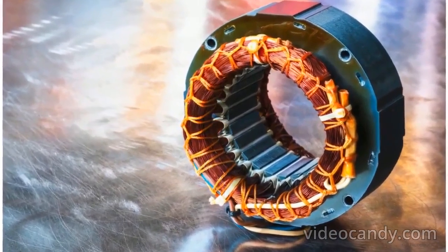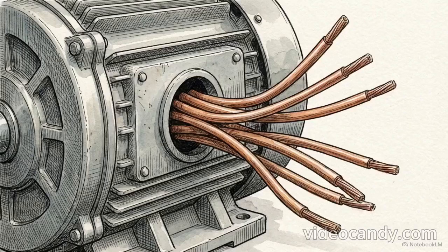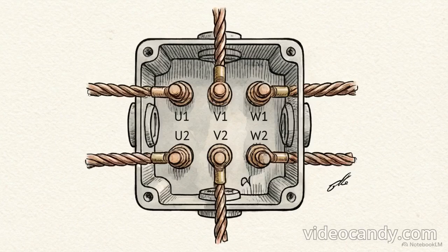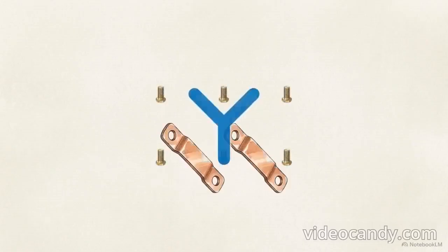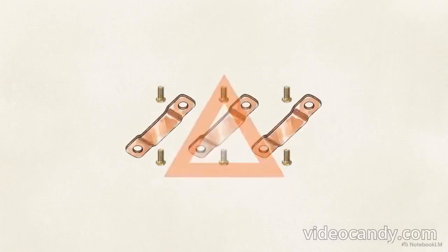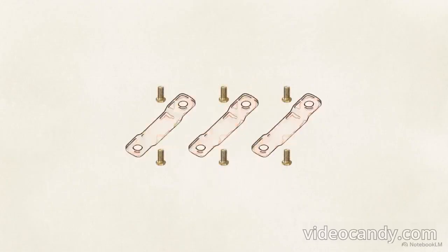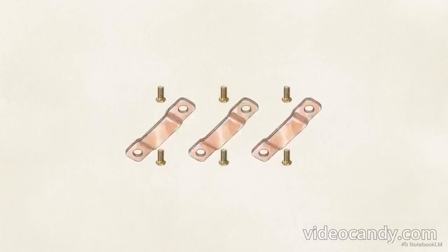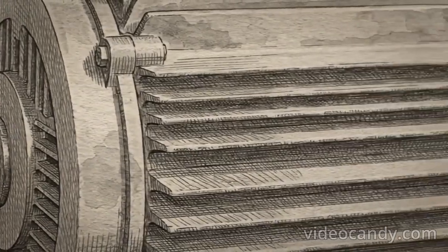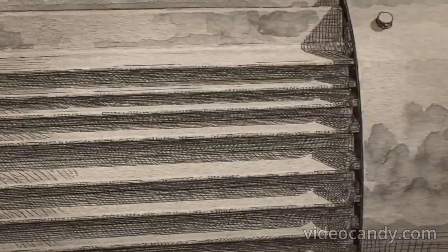In smaller consumer motors, these coil ends are permanently soldered together inside the casing. But in heavy industrial applications, specifically those utilizing star-delta starters, all 6 ends are deliberately kept separate. They are routed out of the stator and gathered together inside an external terminal box, waiting to be configured. Leaving these 6 terminals exposed and independent is the non-negotiable hardware requirement. It is what makes dynamic, mid-operational electrical reconfiguration physically possible.